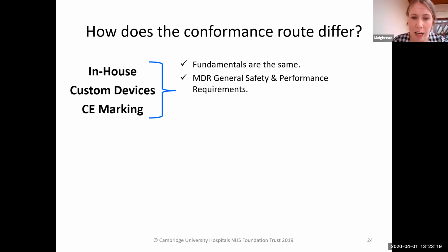In terms of our design process, each device, irrelevant of whether it was an in-house or a CE marking, would still go through the same process, and the fundamentals of that are still the same. Each of those does have to comply with the general safety and performance requirements. Because that list is so expansive, there's very little documentation or activities that you're exempted from. If it was an in-house or a CE marking, they still have to be completed.